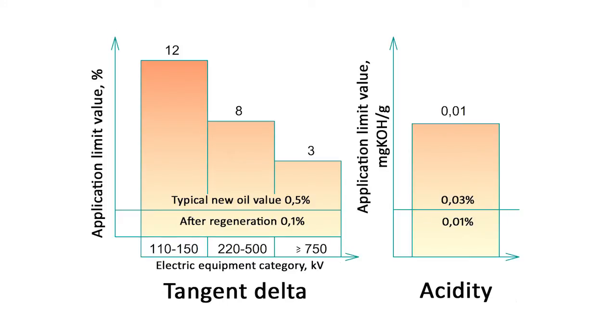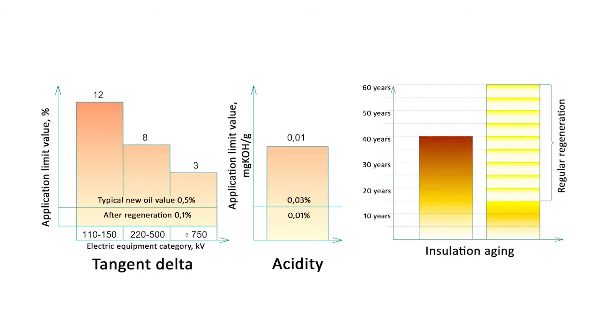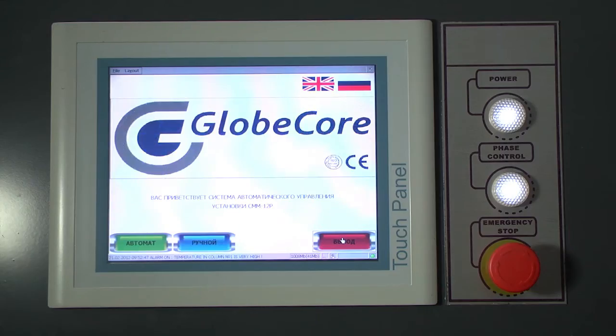This technology allows regeneration of oils directly in the transformer. While regenerating the oil in the transformer, sediment and sludge are dissolved and removed from the transformer. Regeneration extends transformer life significantly while providing the required specifications. Fuller's Earth can be reactivated up to 300 times. Reactivation restores absorption ability of the media. Sorbent is reactivated within the machine — no unloading is required. The reactivation process is safe and has significantly lower energy costs. Treatment is fully automated and operator participation is minimal.